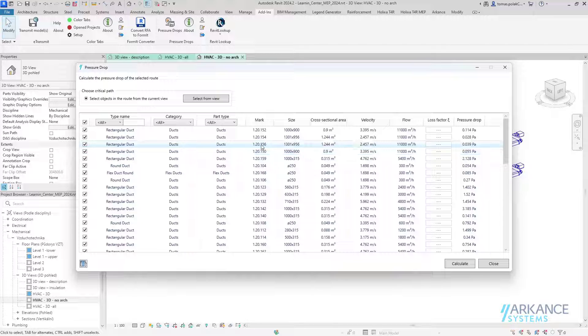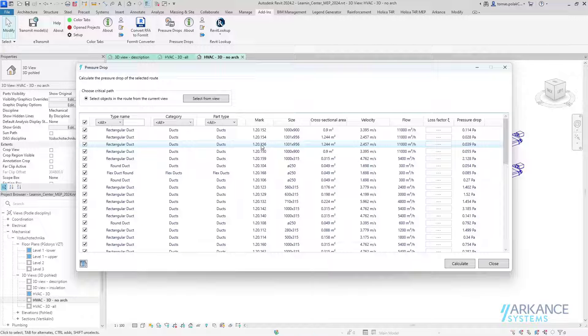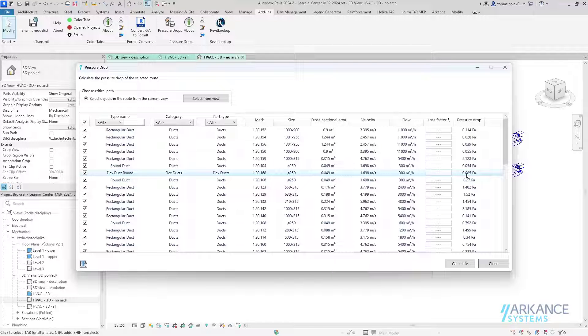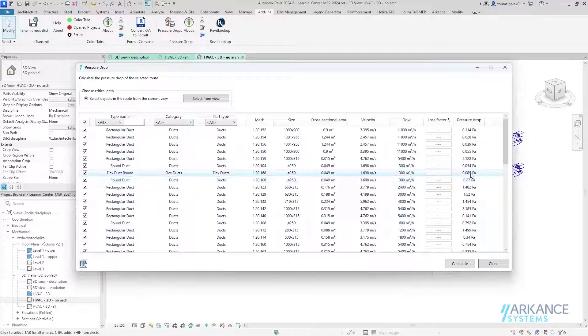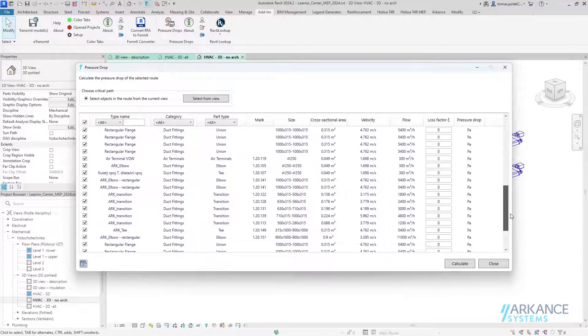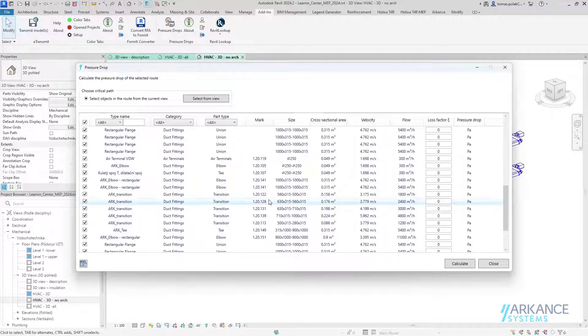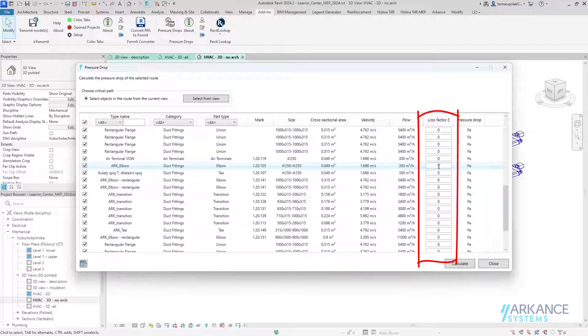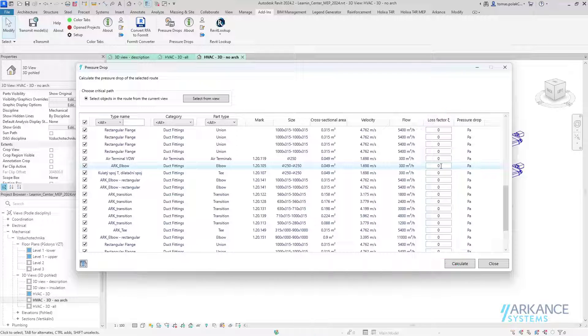What we can see here is that for straight and flat ducts, the pressure drop is calculated automatically and users cannot input the loss factor because this calculation is correct. But when we look at other parts, such as fittings, elbows, transitions, unions, etc., these have the option of users inputting the loss factor.